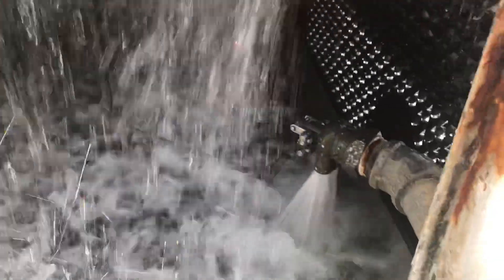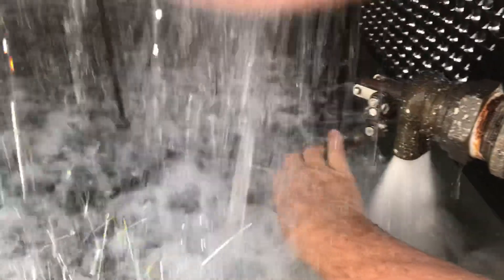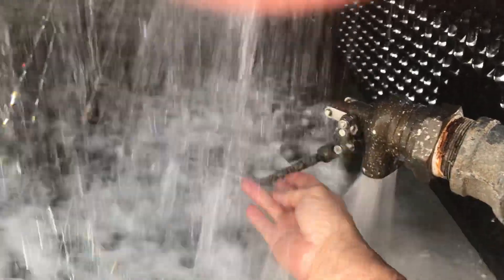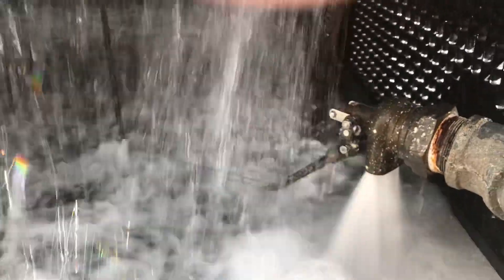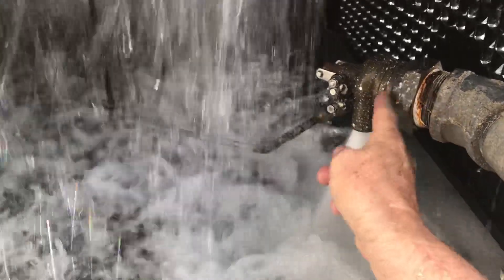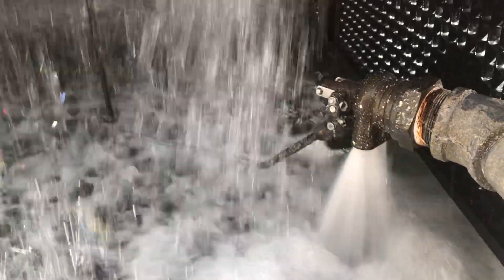I've done a little bit of pre-testing. If I reach inside, I think it's working — we'll see if it shuts off. It should have bounced back down because the water level is not that high. It seems to be working, but when I pushed it up to shut off, it should have dropped back down to the water level. There's probably something on the inside due to age that's sticking and needs to be replaced.